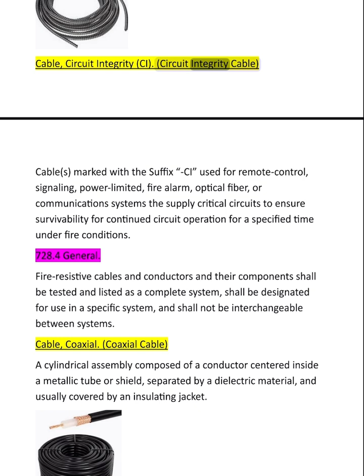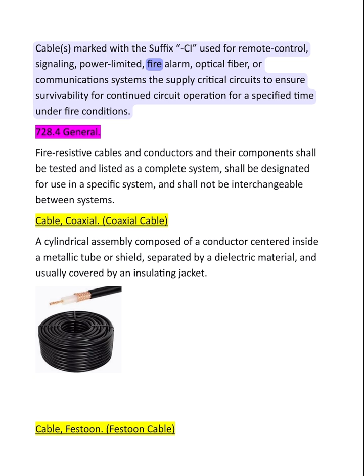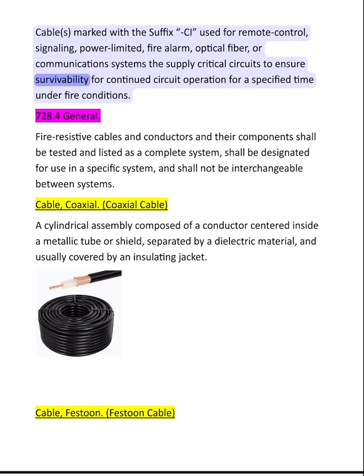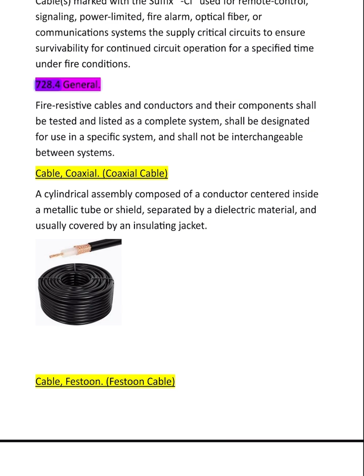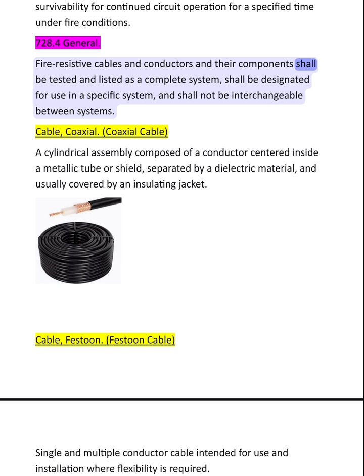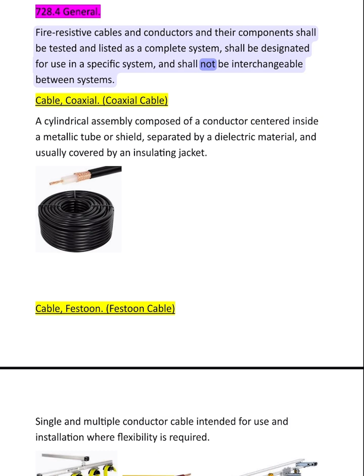Cable. Circuit integrity CI. Circuit integrity cable. Cable(s) marked with the suffix -CI used for remote control, signaling, power-limited, fire alarm, optical fiber, or communication systems that supply critical circuits to ensure survivability for continued circuit operation for a specified time under fire conditions. 728.4 General. Fire resistive cables and conductors and their components shall be tested and listed as a complete system, shall be designated for use in a specific system, and shall not be interchangeable between systems.